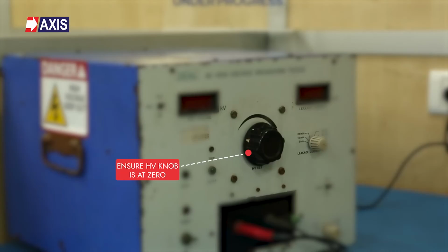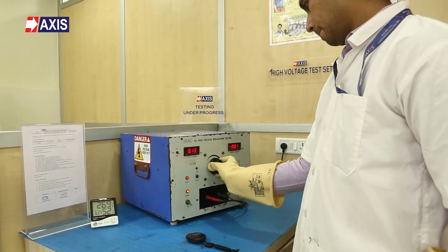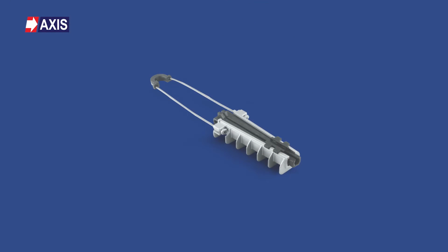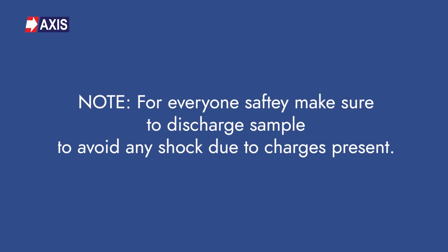As you can see, the HV tester did not trip and sustained a high voltage of 6 kV. This indicates that the axis anchoring clamp is capable of carrying the high voltage levels at the time of fault conditions and it complies with the NFC 33040 2013 standard specification. Note, for everyone's safety, make sure to discharge the sample to avoid any shock due to charges present.